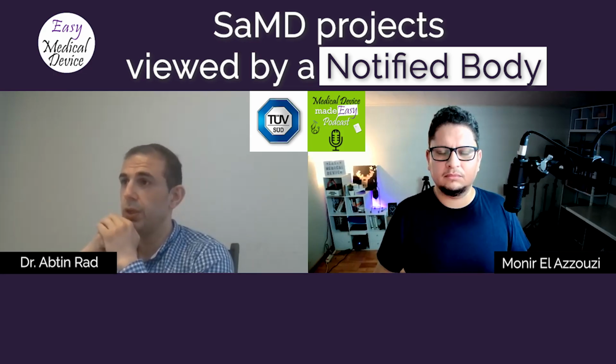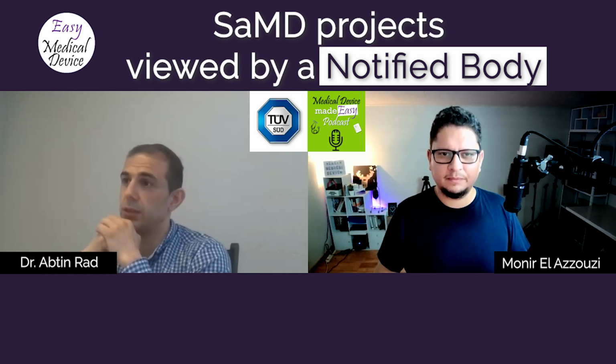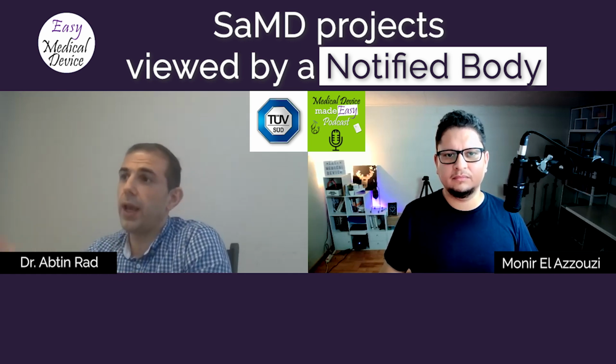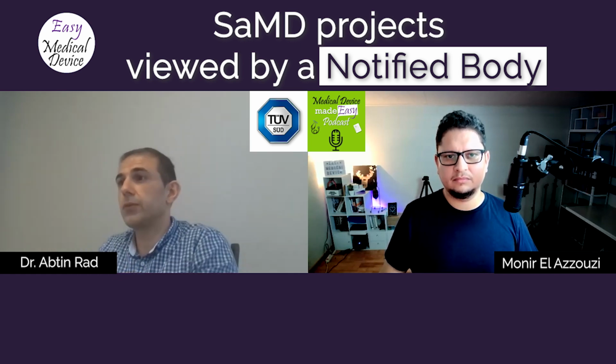So you have Rule 11A. It tells you any software that influences a therapy or diagnosis falls within Class 2A. So just remember the definition: every medical device software that influences diagnosis or therapy falls within Class 2A. And if you go back to MDR Article 2, you see this is basically the definition of medical device software. And by this, since you have the definition of medical device software in Article 2, found in Sub-Rule A, any medical device software must start with Class 2A.